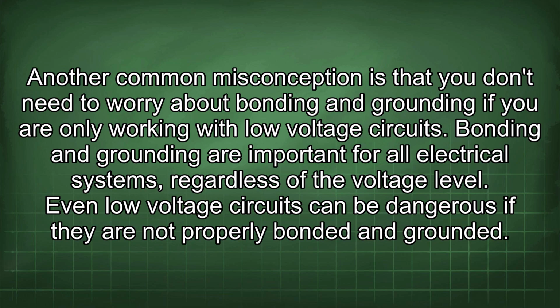Another common misconception is that you don't need to worry about bonding and grounding if you are only working with low voltage circuits. Bonding and grounding are important for all electrical systems, regardless of the voltage level. Even low voltage circuits can be dangerous if they are not properly bonded and grounded.